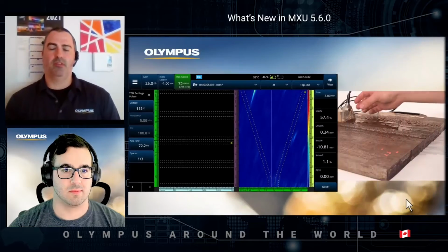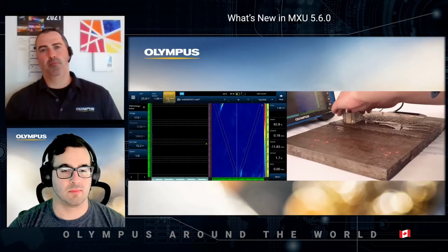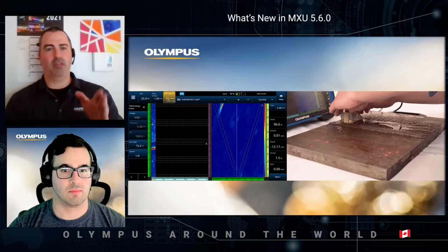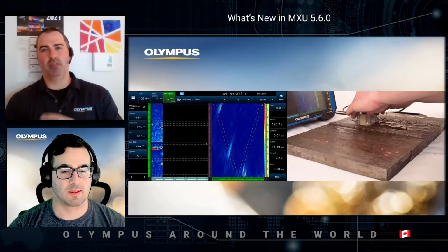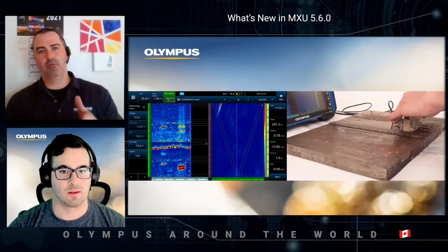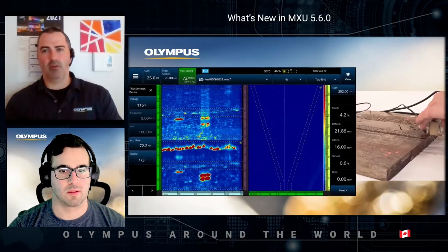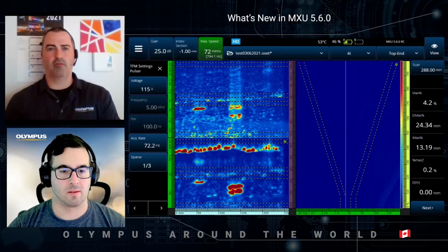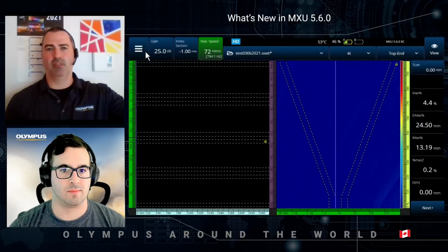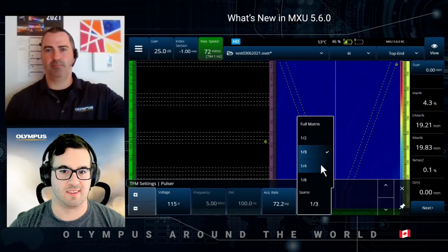Correct. So this acquisition strategy with TFM basically, instead of firing every element individually from the 32 element probe, now we fire 1 out of 2, 1 out of 3, 1 out of 4. So we can get greater acquisition speed by reducing the number of pulsing elements, but we keep a very good TFM signal by still receiving the signal on all of the elements individually.